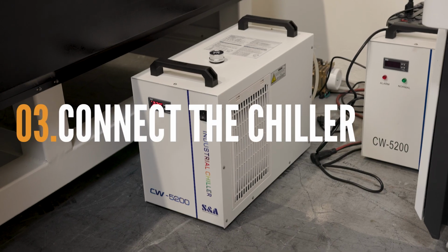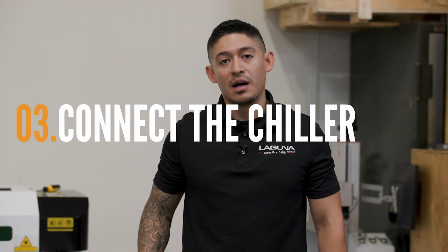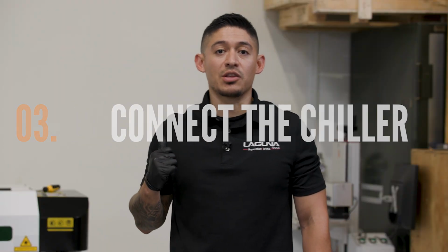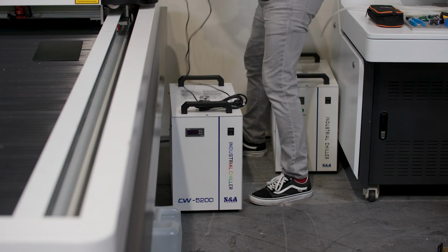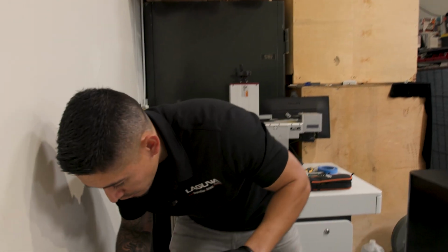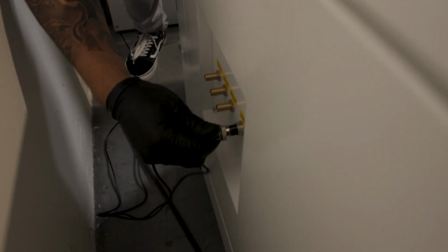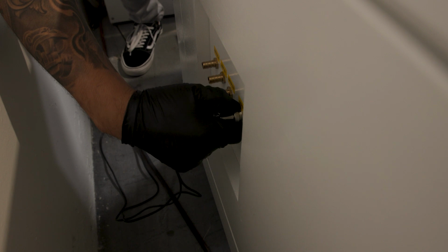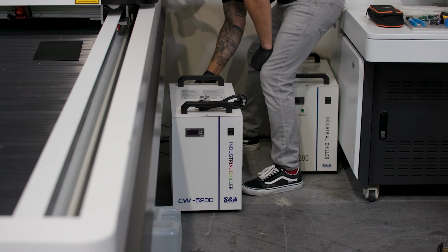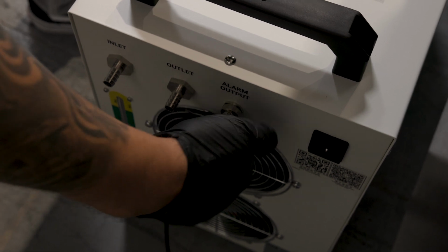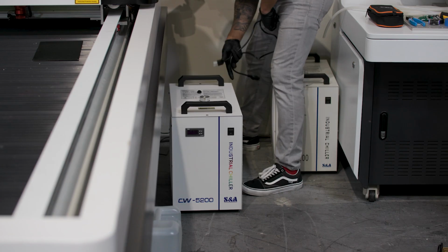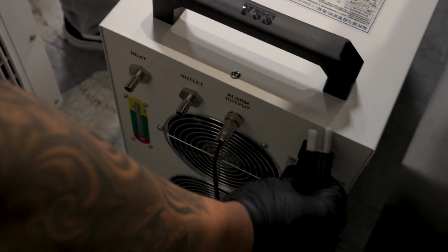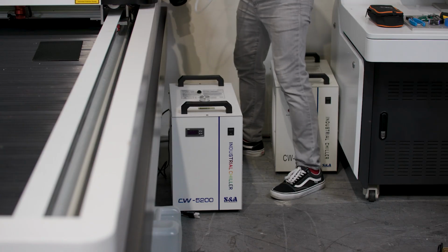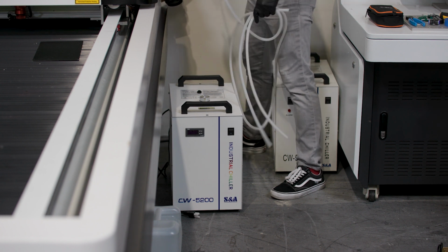Okay, so the next thing, once you get your tube mounted onto your gantry, is going to be connecting your chiller to the machine. That way it gets the water in and out from the tube. Make sure to have distilled water in order to get the chiller filled up. Let's get started. All right, so first thing we want to do is connect your sensor to your machine.